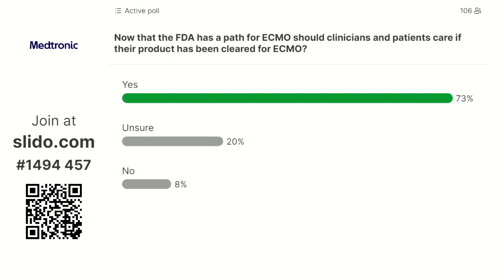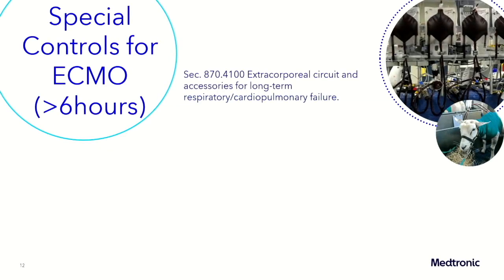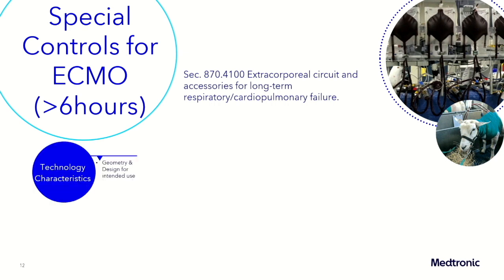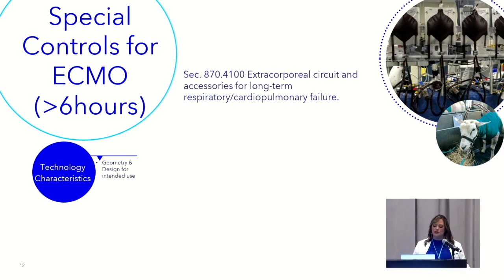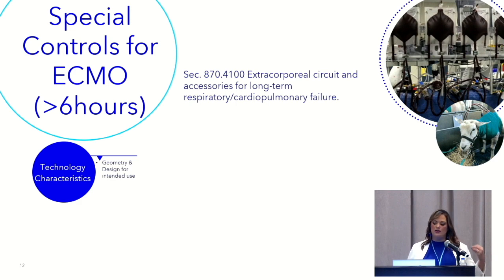What does it mean when you have a product that comes to you? When they developed this ECMO indication, it had very specific special controls that were required in order to bring products to market. We're going to look at some of those so you better understand it today. It's something I really didn't understand until I joined and started doing a little more research on this. The first requirement under this new regulation was technology characteristics. What does that mean? It means that the geometry and design are for the intended use. So I no longer can take an oxygenator that's intended for cardiopulmonary bypass and just pop it in for ECMO. I need to think about what that means. If we're going to have long-term use, if I have corners that are going to be static, or a cannula that's going to move, that's important, right?